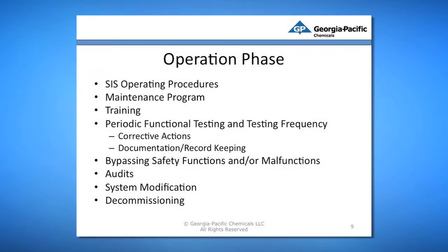A training plan was also implemented to assure ongoing capabilities of operations and maintenance resources, so the training will be ongoing. Periodic functional testing is also required to assure that the desired SIL level is maintained. These tests could include partial testing, valve testing, full testing, whatever parts you have in your safety instrument systems. Any deficiencies found during testing have to be fixed and documented.